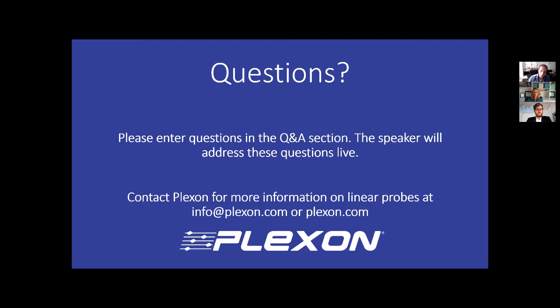Thank you. I think you may have already addressed this, but is the headstage connector at the end of the pigtail held by something? I'm assuming it's not free floating. If it is, did Plexon make that, or did the lab put it together? So you're correct, it's free floating there. The pigtail end is really just to get that connector out of the way, and you can hang that any way that you want. One way we've done it is put it over the back of the microdrive. There's screws there. We just throw it over the back. There's no concern about it pulling on the probe. It may look big in that picture because I took it close up, but these things are quite small, and they're not heavy. So you're really not putting a whole ton of strain on the probe at all.